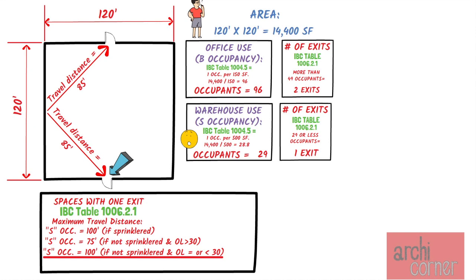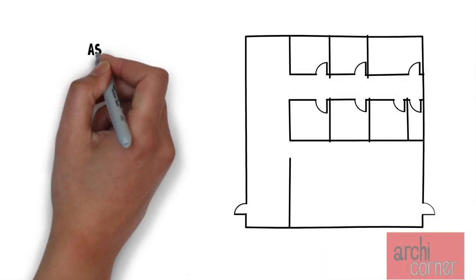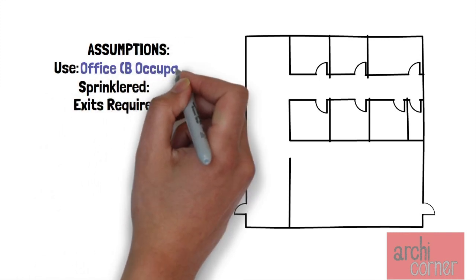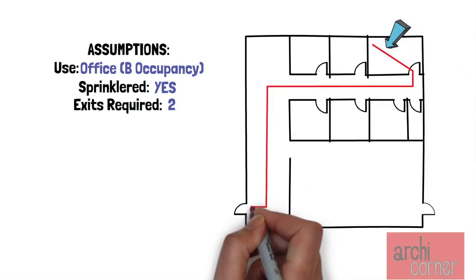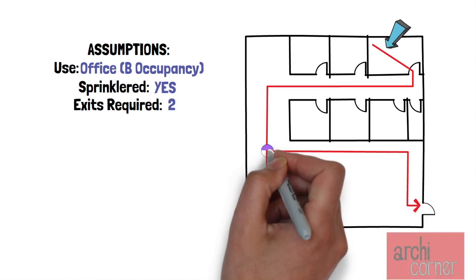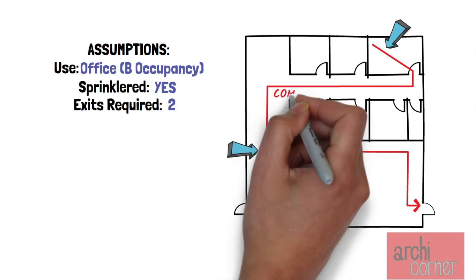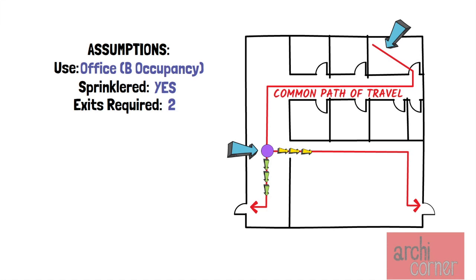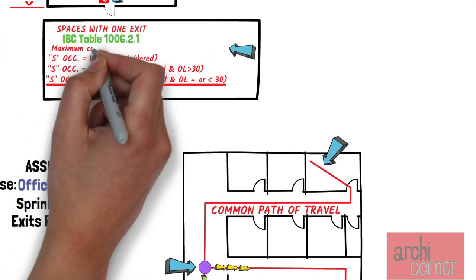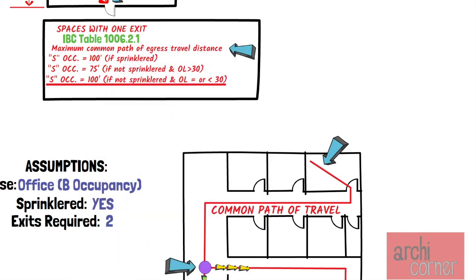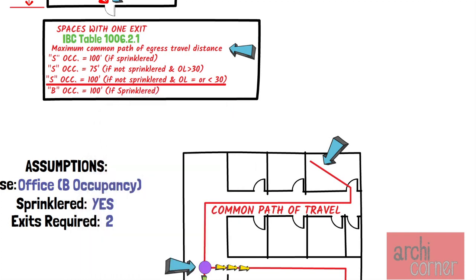Now that we understand path of egress travel distance and how it affects the number of exits, let's discuss what happens to travel distance when you do need two exits. Assume this space is used for office, it is sprinklered, and it requires two exits. Notice that even though there are two exits, a person must travel up to a certain point before having the option to decide which direction to take. This first portion of the path of egress travel is what is known as the common path of travel, and that is also what IBC Table 1006.2.1 limits — the complete header for this section is titled 'Maximum Common Path of Egress Travel Distance.' The common path of travel for an office use or B occupancy is limited to 100 feet in a sprinklered building.